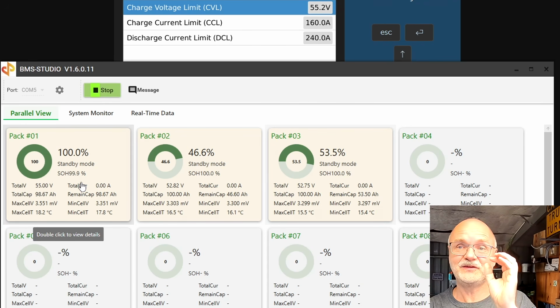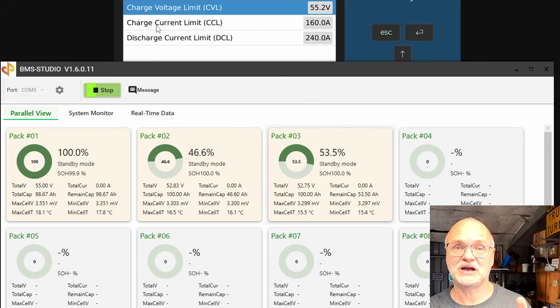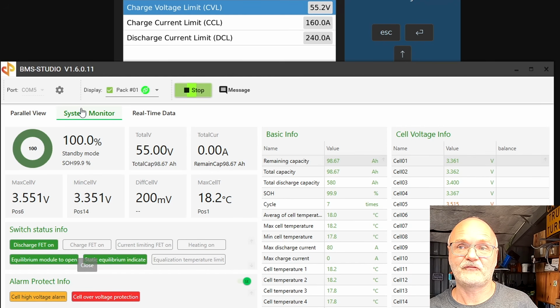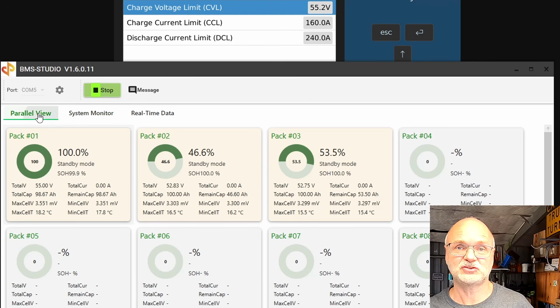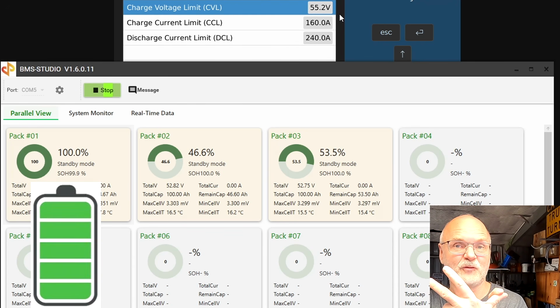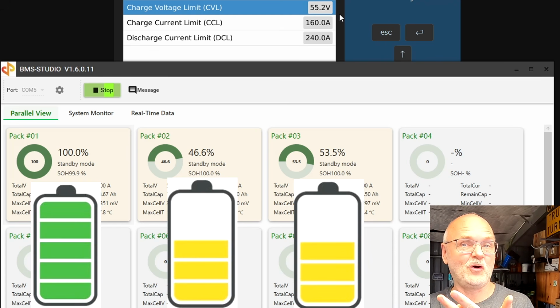If we only had this battery connected, it would set the charge current limit to 0 amps because it's full, and it even has an over-voltage protection, so the charge MOSFETs are off. But there's communication between all these BMSs, and it still tells the charger, hey, you can still charge with 160 amps, so 2 times 80 amps instead of 3 times 80 amps, because I am full but the other 2 are not.